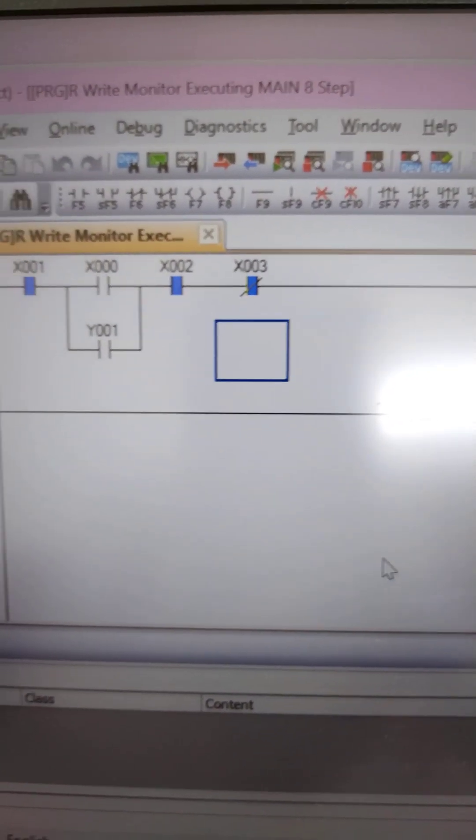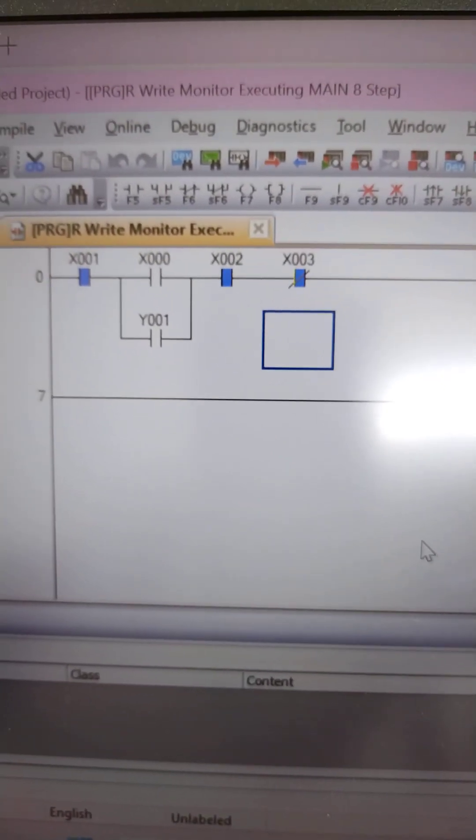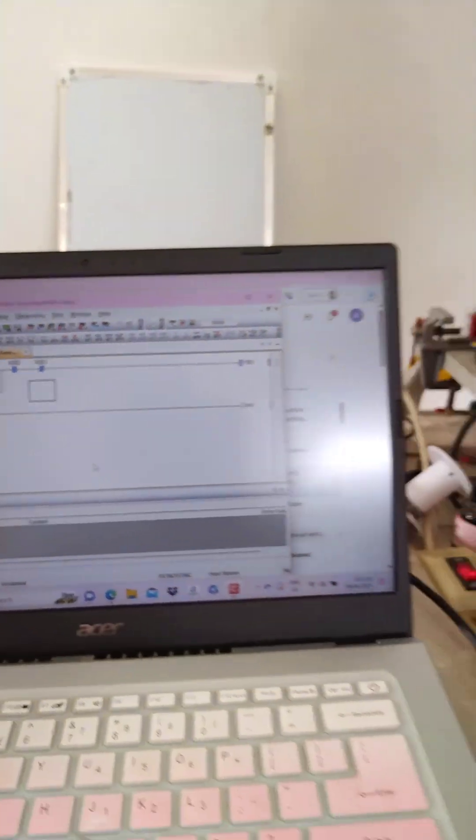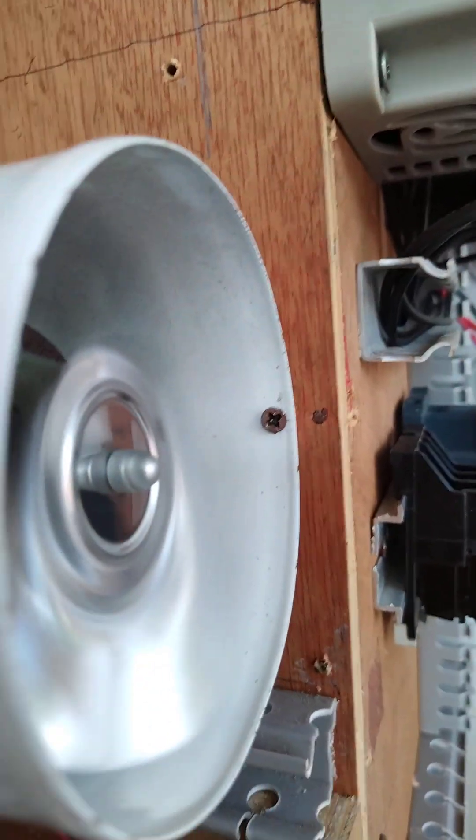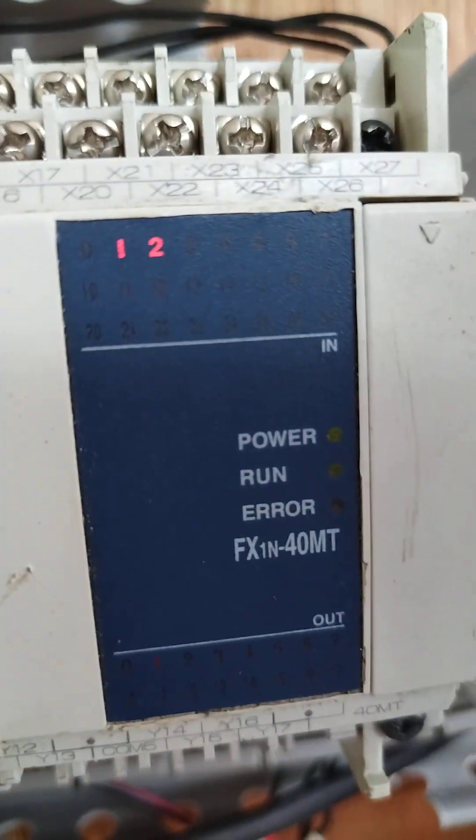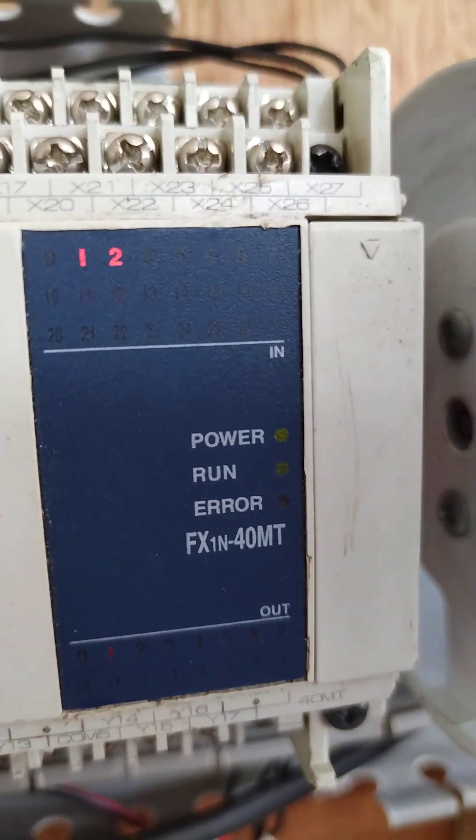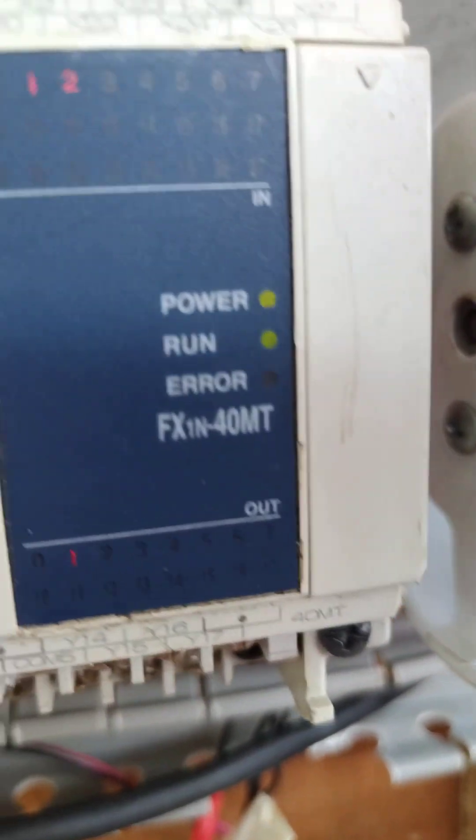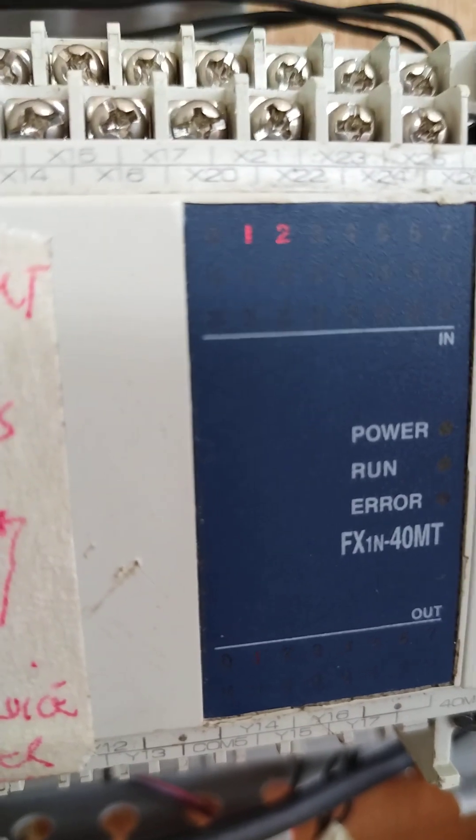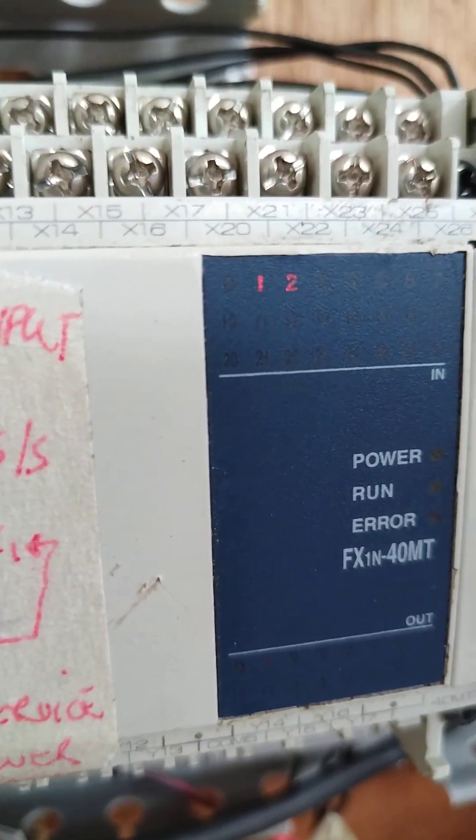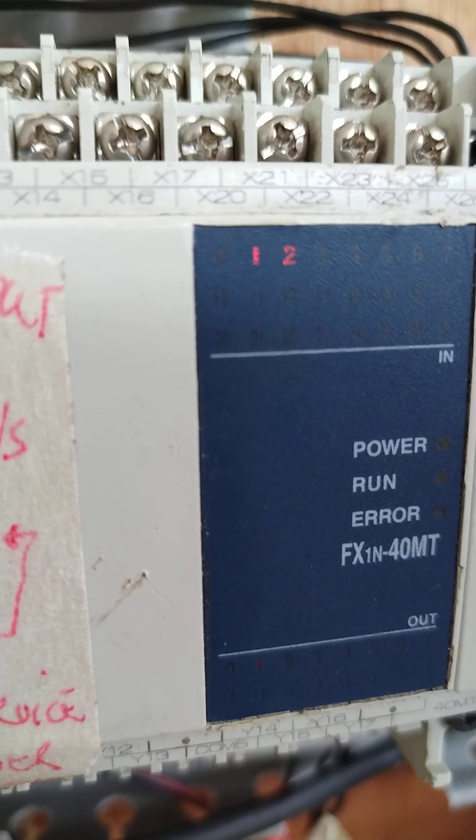So let me simulate or let me operate it. I'm pushing now... As you can see, push button is momentary. The fan is already running. As you can see, it's already running. Then you can see also in the PLC itself, one and two is closed. One is our selector switch in auto. Then two is our stop push button. My output is there. I'm using Y1, so there is a light, meaning it's activating my load or my coil.